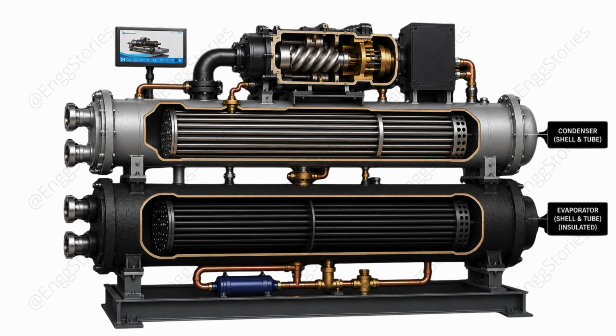Now, let's understand the chiller system. Whether it's a water-cooled chiller or an air-cooled chiller, both work on the vapor compression refrigeration cycle. Let's start with the compressor. The refrigerant enters the compressor as a low-pressure, low-temperature vapor. The compressor compresses it, increasing both its pressure and temperature. Now, the refrigerant leaves the compressor as a high-pressure, high-temperature vapor and moves to the condenser.